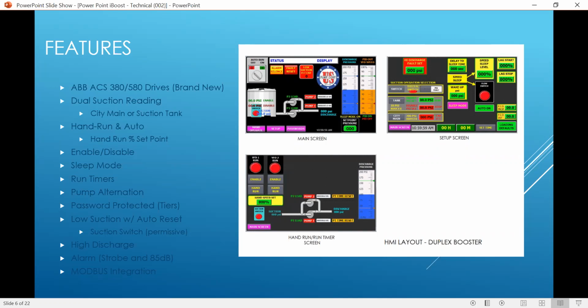And then about the Modbus, if you could get into that just a bit. Yeah, so our standard is Modbus, and we can interface to basically any controls using that method. I know a lot of people tend to use BACnet. We can still go that route. Regardless, we would need an interpreter between the BACnet and the Modbus, but we can connect to any type of BMS.